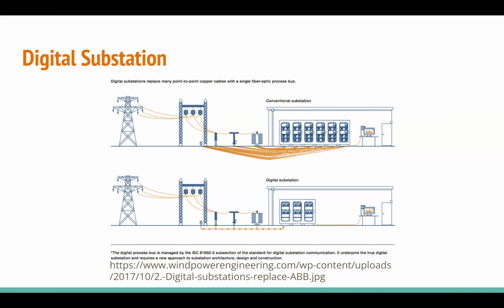Can we use conventional equipment in a digital system? A lot of relays support both, so you can have conventional hardwired signals and digital communications built into them. But there are newer relays that are only for digital substations, where they don't have any physical inputs on them at all.